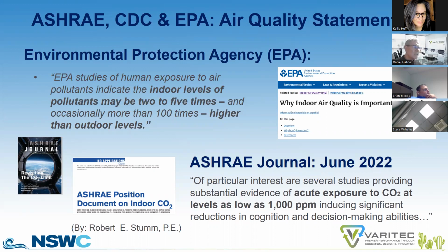The federal government has done previous studies that have come up with a value of CO2 levels up to 5,000 parts per million providing safe environments. However, the International Space Station's biggest challenge to astronauts is CO2 concentrations and how that can result in headaches and just a general sense of lethargy at the CO2 concentrations they're subjected to.